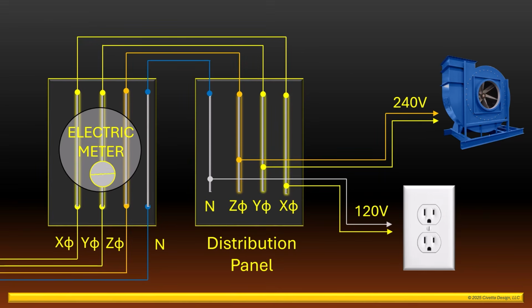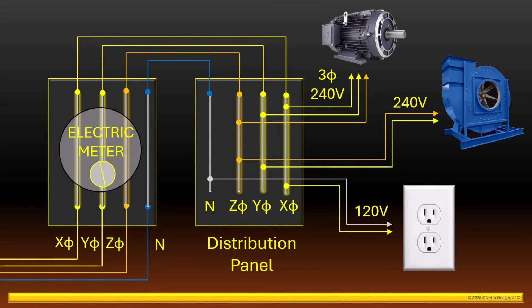All three phases are used to provide three-phase 240 volt power, usually to large motor loads like elevators or industrial air conditioning. The anomalous single-phase 208 volts historically has been used to provide power to small single-phase motors.